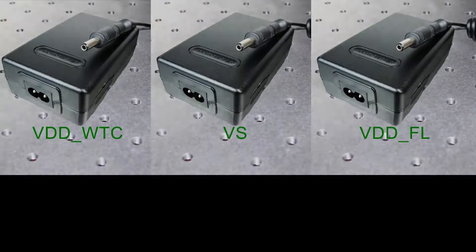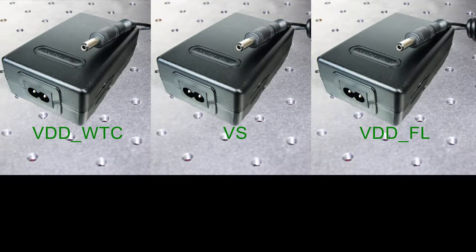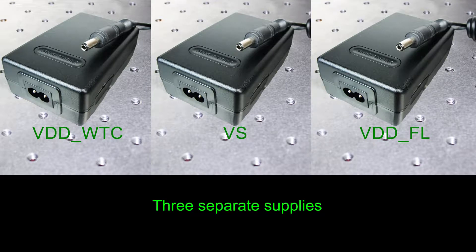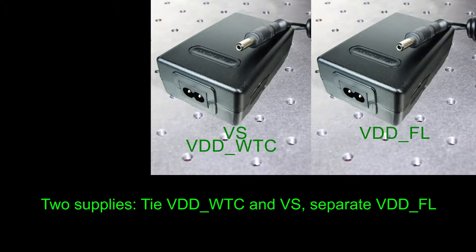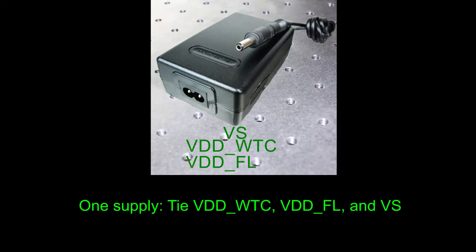The power supplies may be wired in one of three ways: three separate supplies, tied temperature control supplies with a separate laser driver supply, or single supply operation with all three power supply inputs tied.